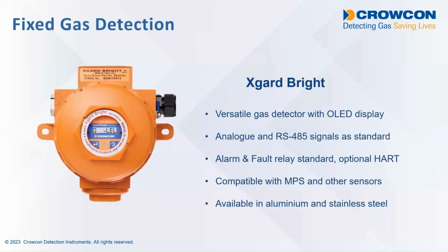4-gas personal monitor. So the Xgard Bright is a fixed point gas detector, permanently installed on site. It has a display so you can see the gas concentration locally. It has analog or RS485 digital signals for communicating with the control system. It has relays on board which can be used to trigger a sounder and a beacon locally. And as I say, it's available with the MPS sensor for hydrogen detection, but it's also available with a carbon dioxide sensor. And we do have some of these instruments in stainless steel enclosures in breweries across the UK.